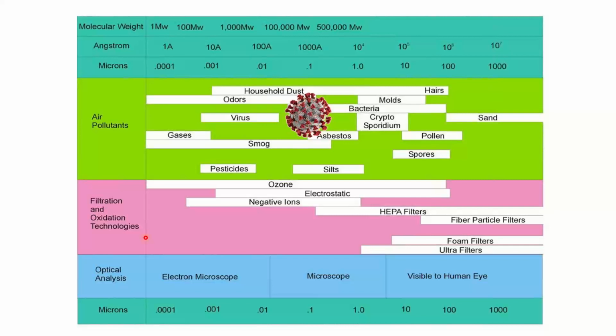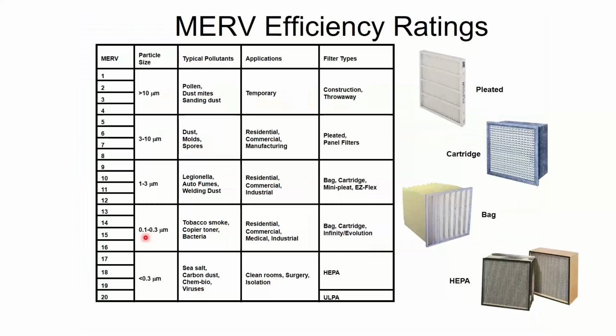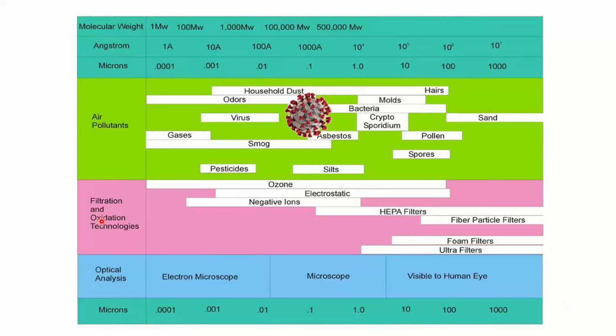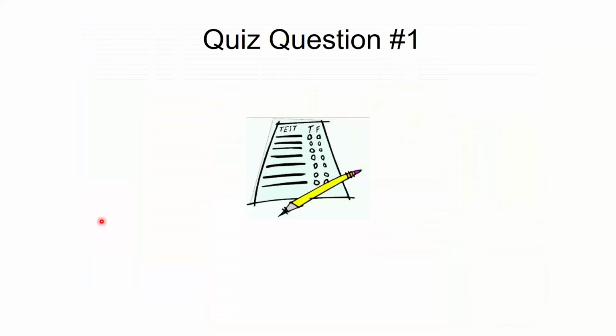So there's our particle. I said it's probably a little bit smaller than 0.1. So MERV 12 isn't going to get it done. I have to jump up to a MERV 13. By the way, if you're wondering about the gap on this chart between the 0.3 and the 1, they only test certain size particles, and it's going to be a percentage of those particles. They don't test exactly 0.8 size particles.